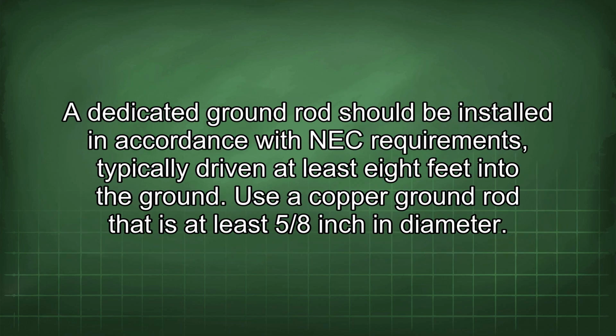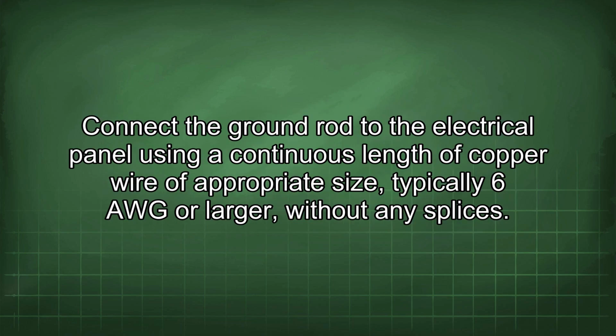A dedicated ground rod should be installed in accordance with NEC requirements, typically driven at least 8 feet into the ground. Use a copper ground rod that is at least 5/8 inch in diameter. Connect the ground rod to the electrical panel using a continuous length of copper wire of appropriate size, typically 6 AWG or larger, without any splices.